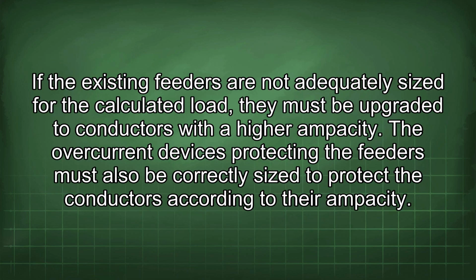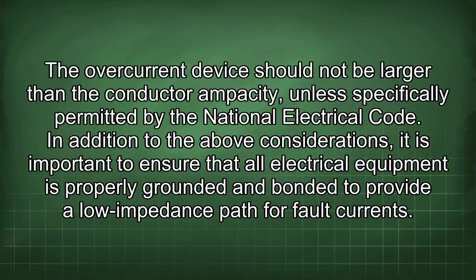If the existing feeders are not adequately sized for the calculated load, they must be upgraded to conductors with a higher ampacity. The overcurrent devices protecting the feeders must also be correctly sized to protect the conductors according to their ampacity. The overcurrent device should not be larger than the conductor ampacity unless specifically permitted by the National Electrical Code.